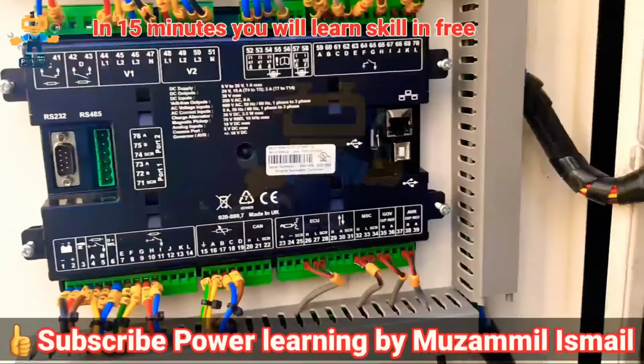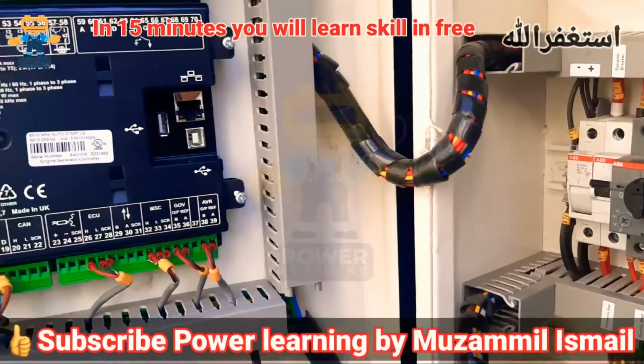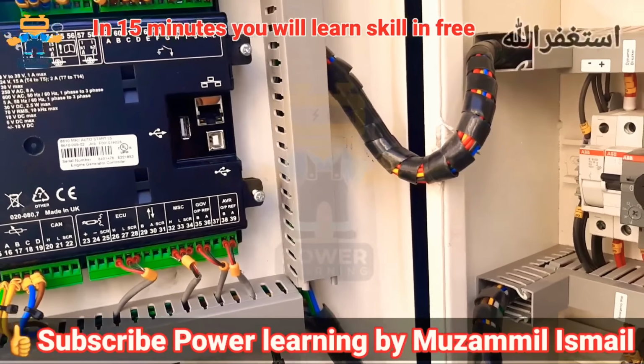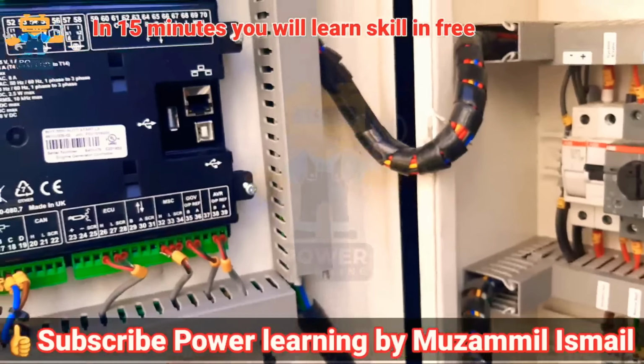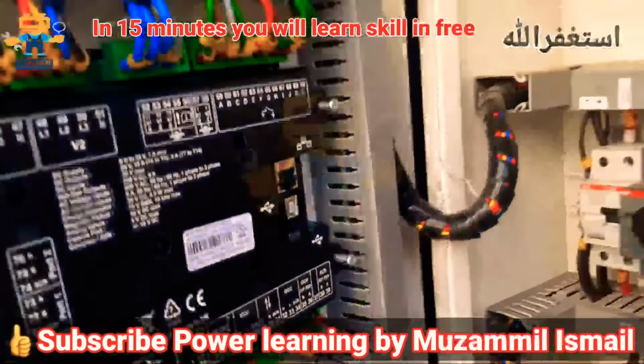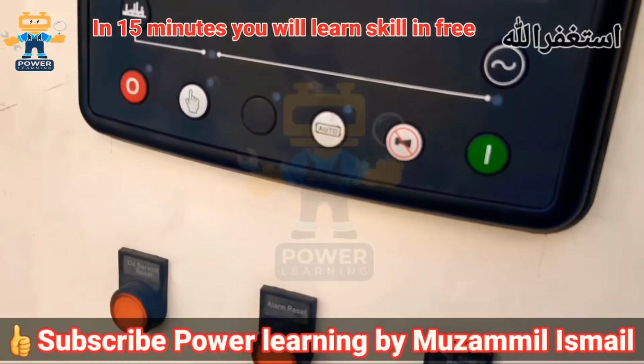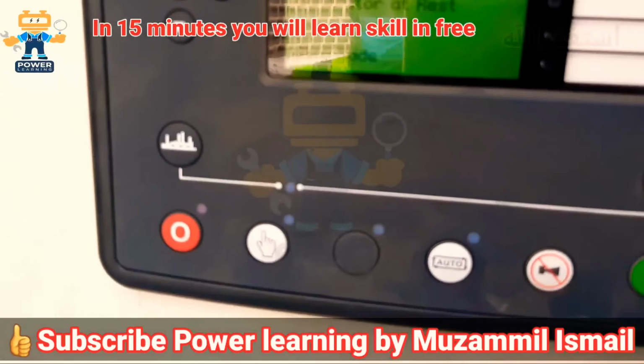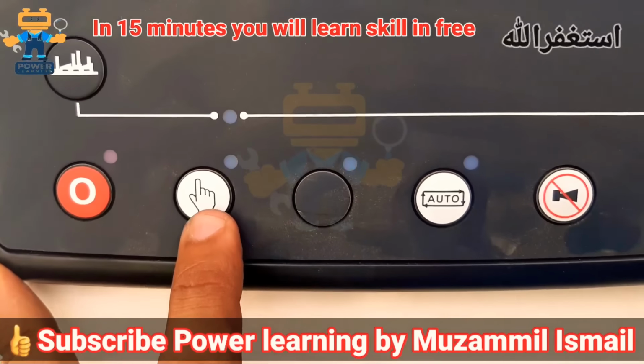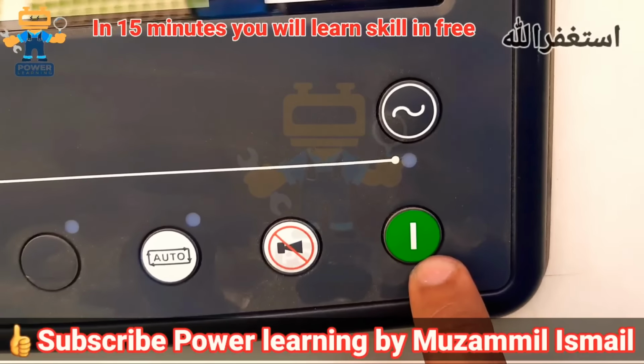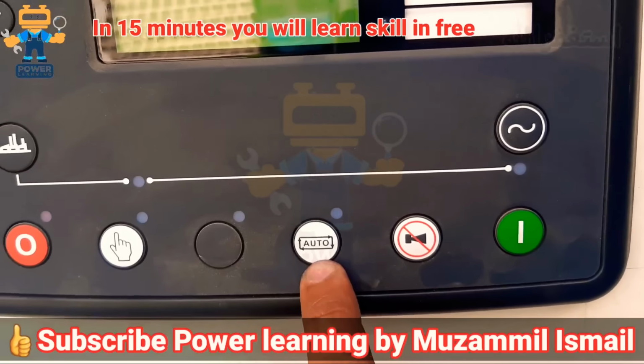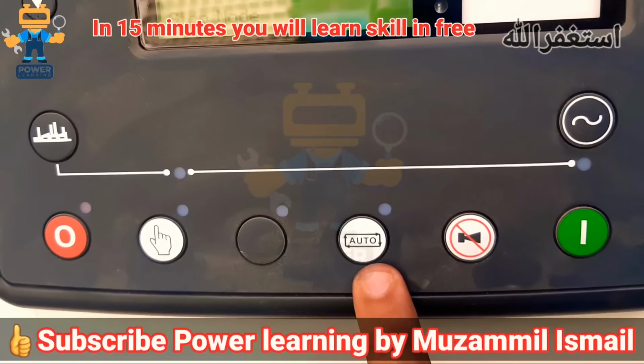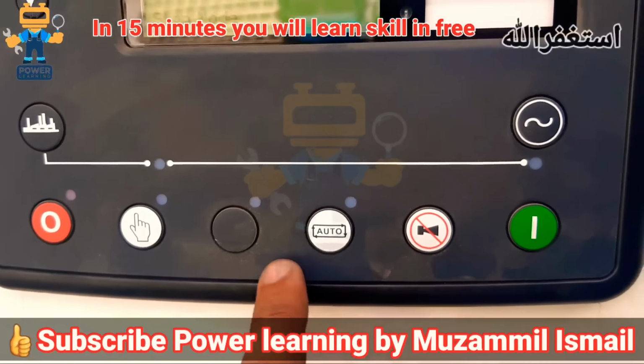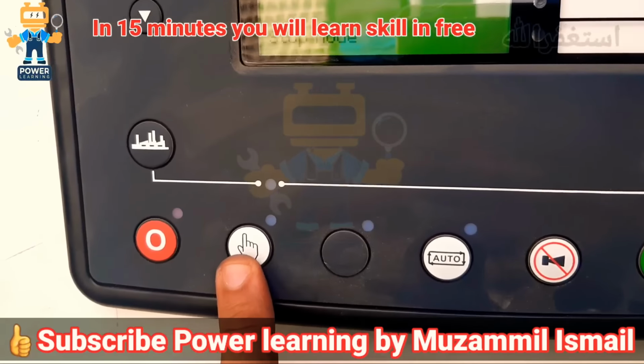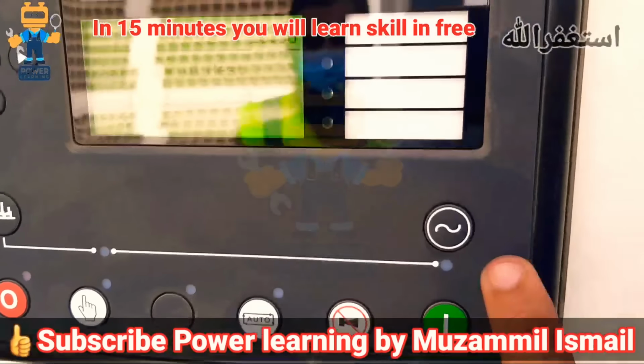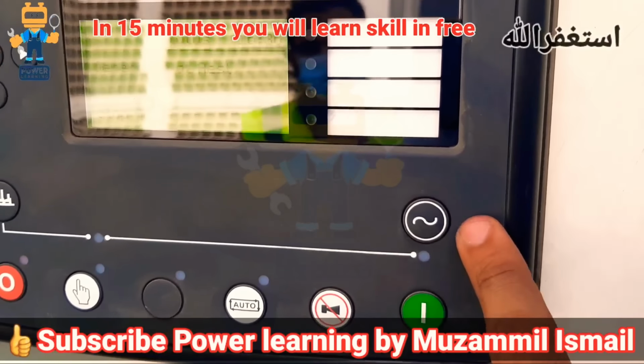This is a very compact size synchronizing panel. Okay, very fully automatic synchronizing, no need to operate so many things, I can just show you very simply now. Okay, if you can see here, this is the controller, this is the stop button, this is the manual mode button, the auto button and the start button. If you want to start the generator on auto, just press auto, the generator will automatically start and close the breaker. Okay, but if you want to start manually, you have to press the manual button, then the run button, and then press the breaker close button, so the breaker will be closed.